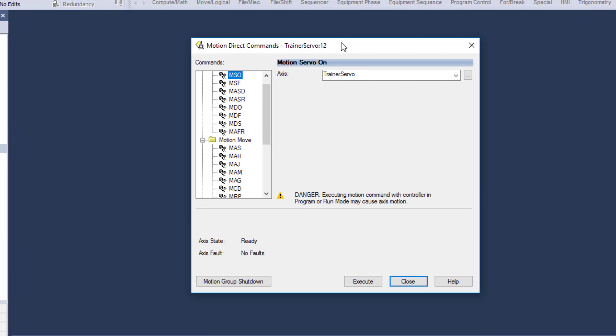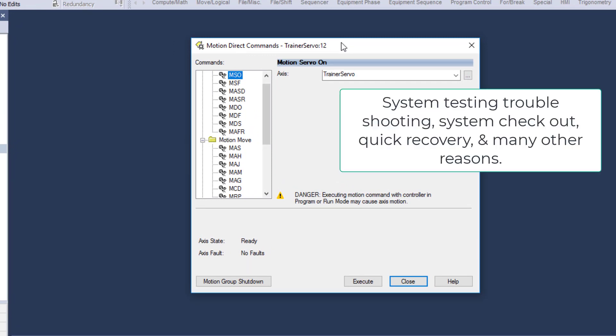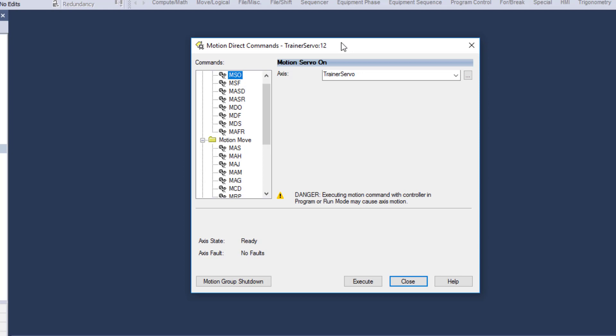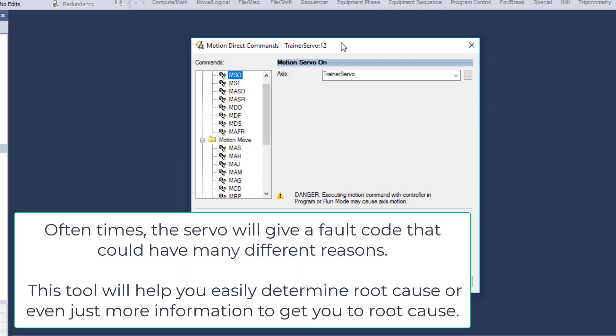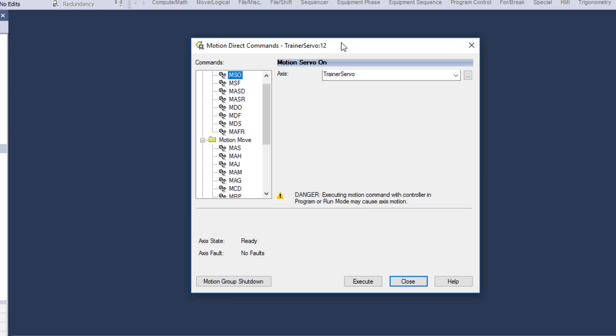I want to talk about a couple of reasons why you would actually use motion direct commands. Well, if you're troubleshooting a servo — let's say the servo faulted out — you troubleshoot the fault and you think maybe it's the motor. It could be a mechanical limitation, like something attached to the motor that is mechanically hitting something and torquing out, or maybe the velocity is too much and it's tripping out when you're stopping it too quickly. If you change the motor, you're going to end up with the same problem if it's a mechanical limitation — something causing an axis feedback issue, like overpower.